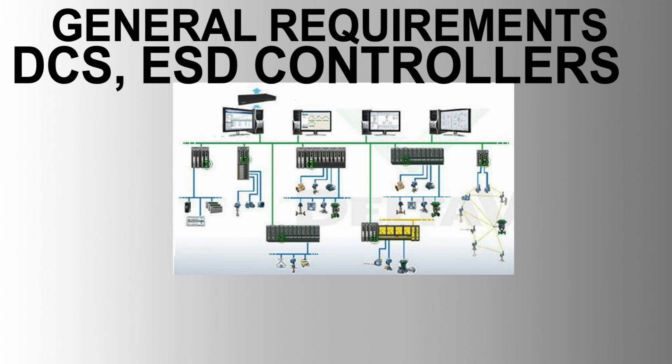Engineering workstations serve as programming and configuration consoles with redundant servers and concurrent access to the configuration database. Capable of modifying programs, performing sequential programming, and configuring regulatory loops. Security features include password protection for configuration data access. System servers, redundant servers for control and database management to ensure no single point of failure. Capable of storing and managing historical data, alarm history, and system configurations. Provide interfaces for real-time and plant information systems integration.